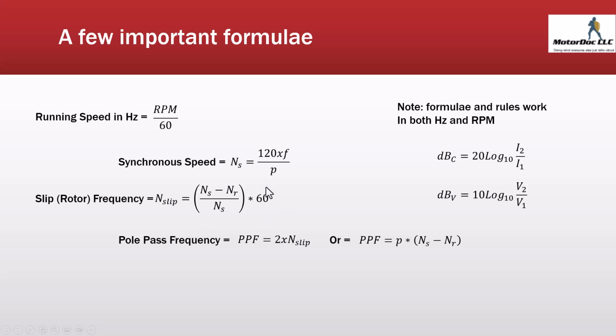The slip frequency is the synchronous speed minus the running speed divided by the synchronous speed times 60. That gives me a frequency, and then I can either look at twice the slip frequency, or I can go the slip times the number of poles to get pole pass frequency. Both numbers come out identical. Now we're going to be showing everything in decibels. In order to calculate decibels for current, it's 20 times the log 10 of the current of interest divided by the primary current at the line frequency. And then for voltage, it's 10 times the same type of formula.